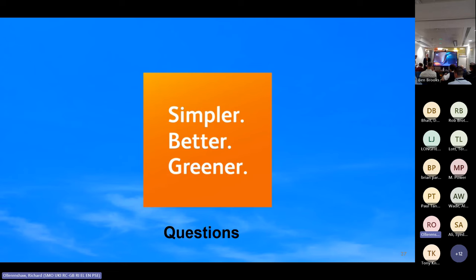It's a really good question. With switching, there is. So if you're going to do what the Japanese do and put switches in so that you can effectively separate a lump of railway, then you can achieve it. The question is brilliant because you've hit on one of the reasons why neutral sections are useful. You can parallel up while keeping a neutral section. But the neutral section has a reliability and a maintenance cost. It is a tricky one to balance.